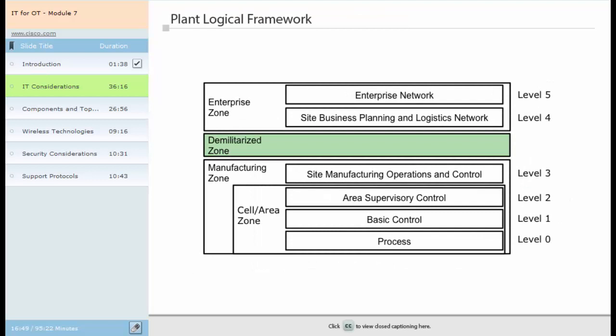Also in this logical framework is a demilitarized zone or DMZ. This zone is inserted between the enterprise and manufacturing zones as part of the converged plant-wide Ethernet architecture developed by Cisco and Rockwell Automation. The DMZ provides a buffer zone where data and services can be shared between the enterprise and manufacturing zones, similar to the way a DMZ provides access to corporate resources shared with the outside world. The DMZ is critical in maintaining availability, addressing security vulnerabilities of the manufacturing environment, and abiding by regulatory compliance mandates. In addition, the DMZ allows segmentation of organizational control for the network.